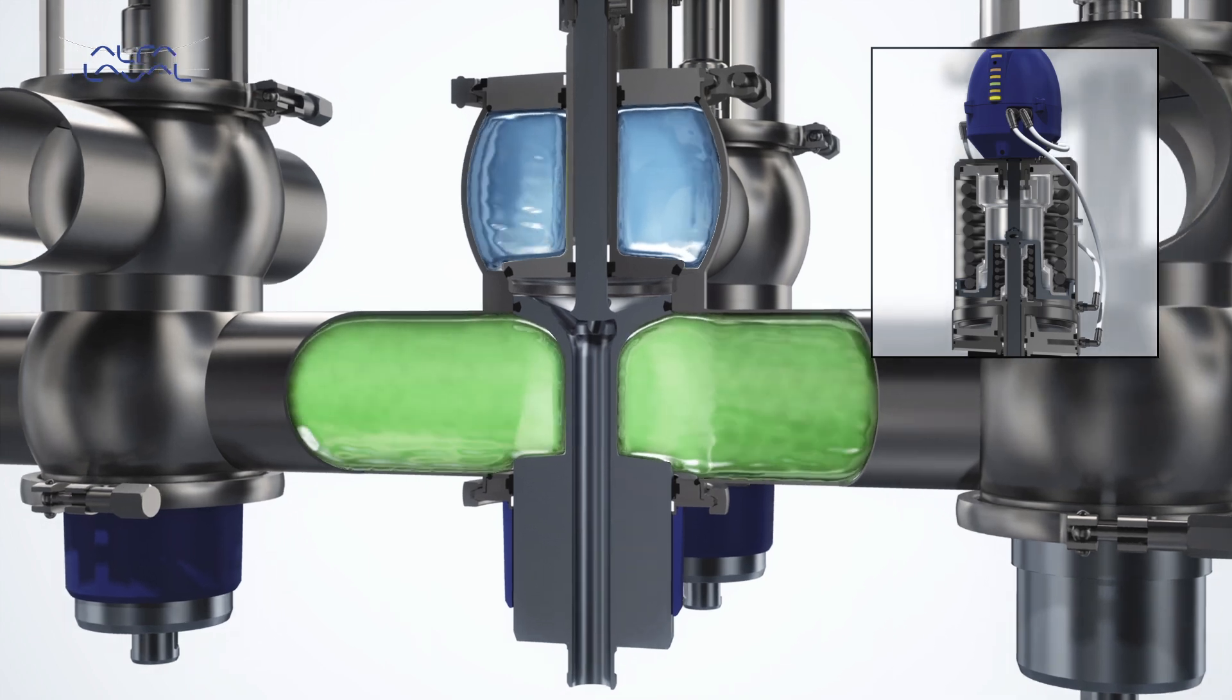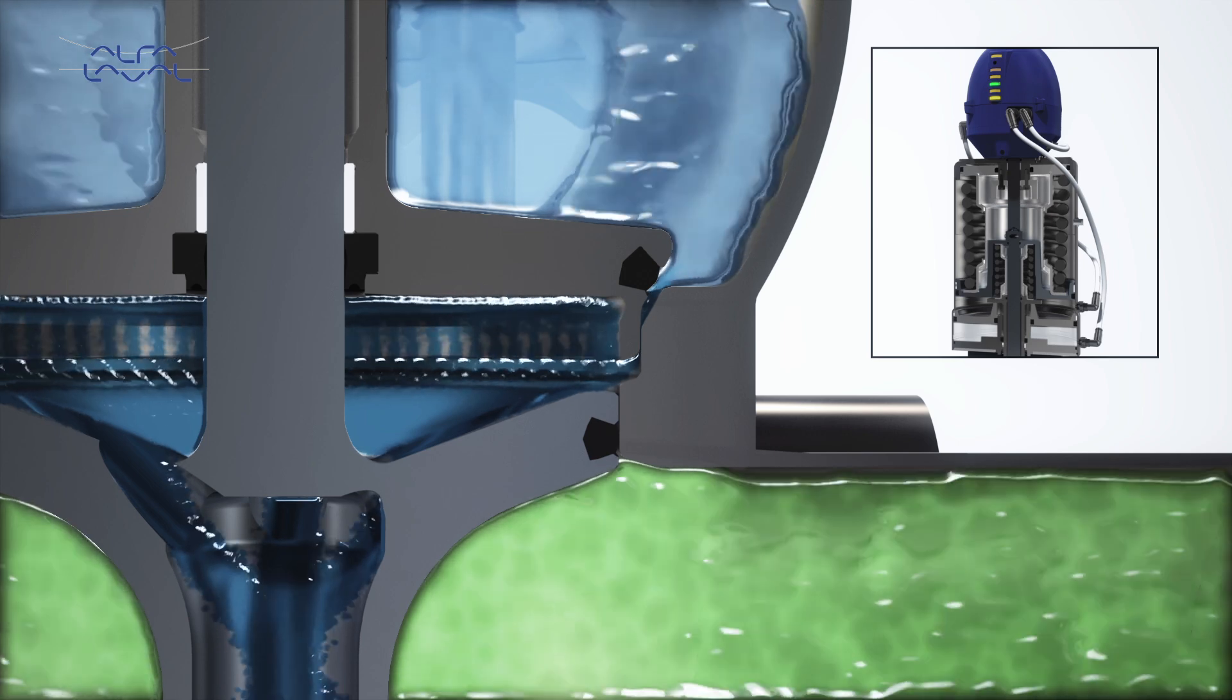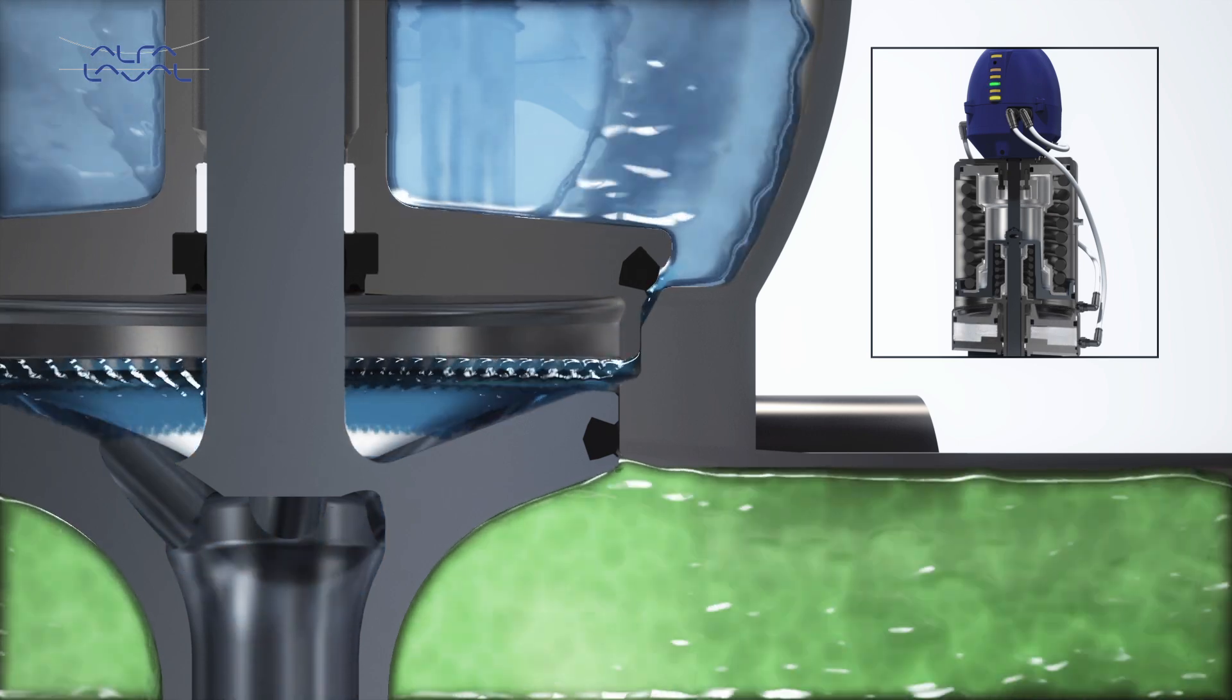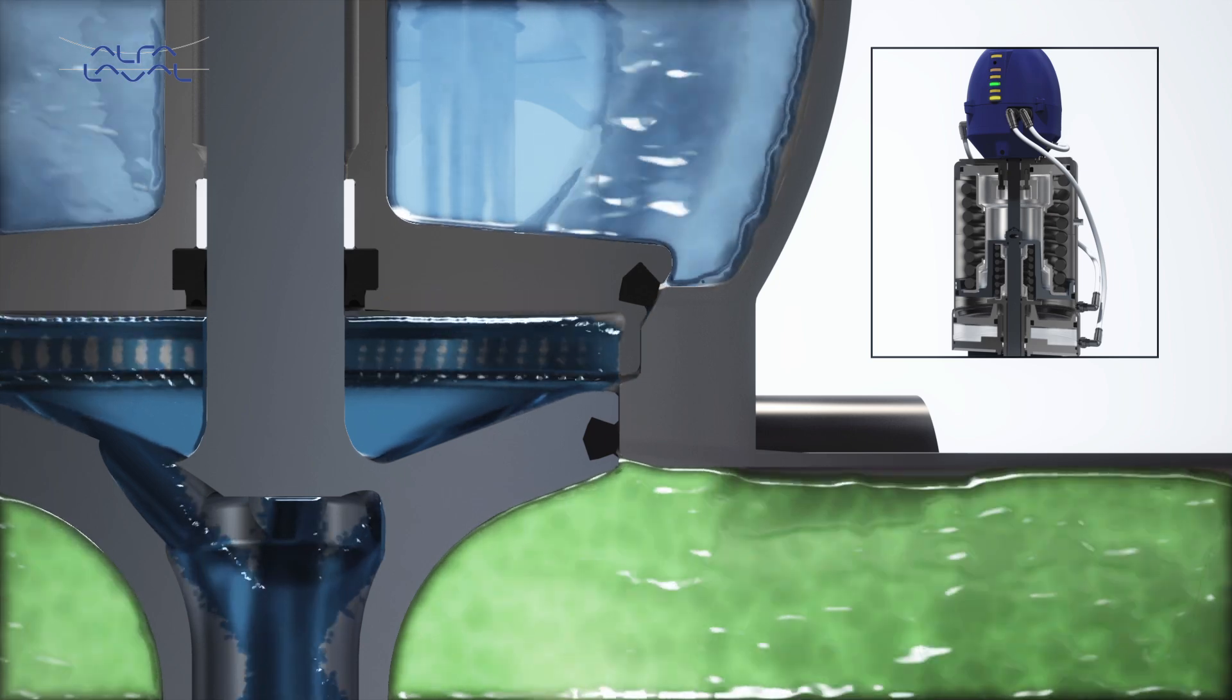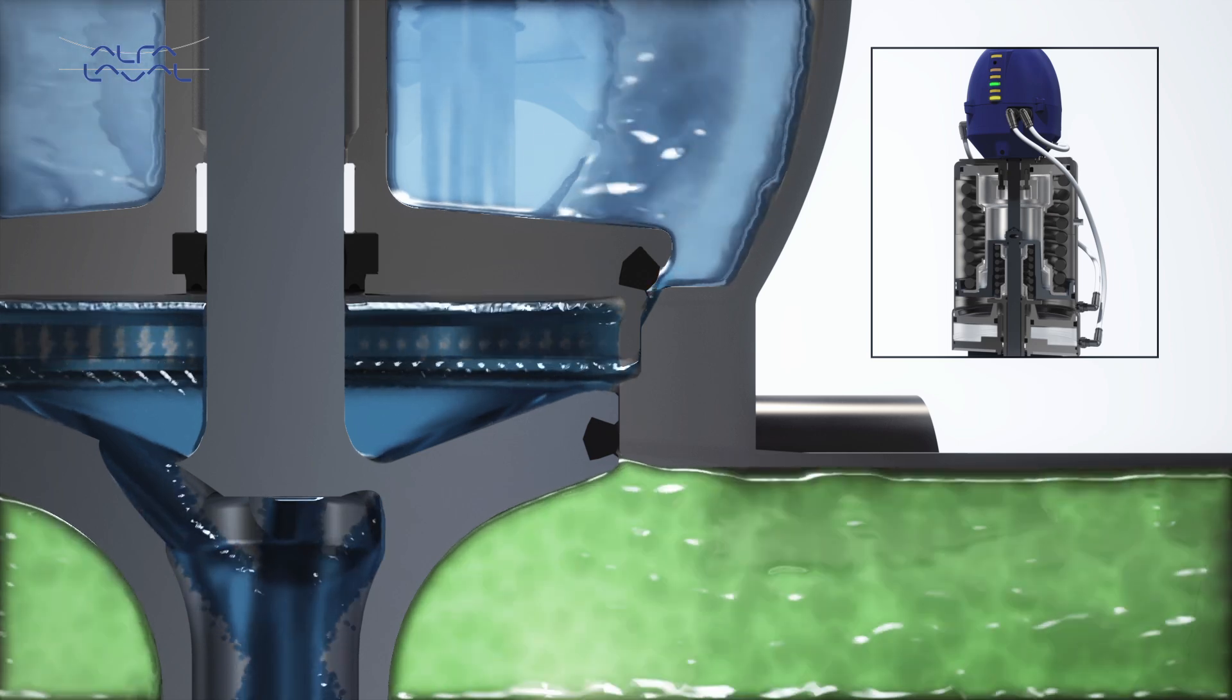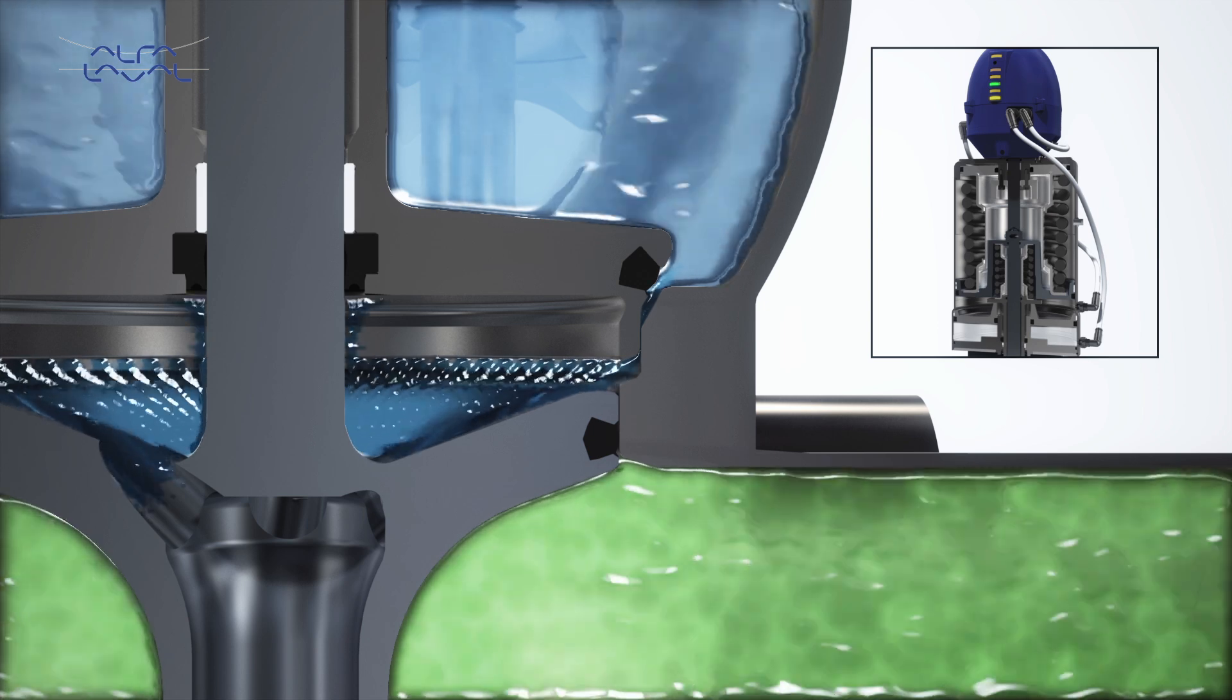Metal to metal stops in the actuator ensure precise positioning of the valve plug in the body, thereby ensuring a throttling edge, which enables exceptionally fast-acting cleaning during seat lift. This speeds up the cleaning process by creating high turbulence and scrubbing effects, making very efficient use of a minimal amount of CIP fluid.